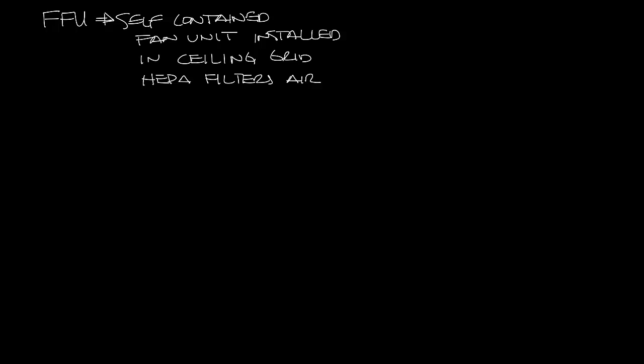So fan filter units basically look like this. They fit in the 2x2 ceiling grid. They may have an inlet that's ducted to supply air but most of the time they pull air from an open plenum.